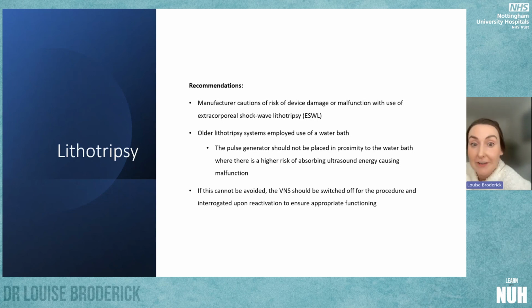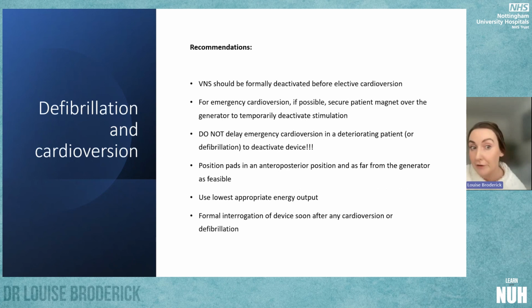Effectively, to deactivate the device, there is a risk of malfunction of the device associated with it. With regard to defibrillation and cardioversion, the guidance is similar to other cardiac implantable devices. We should be formally deactivating it before elective cardioversion. In an emergency, if possible, secure the patient magnet to deactivate the device temporarily, but obviously do not delay any emergency procedure, cardioversion or defibrillation to deactivate the device.